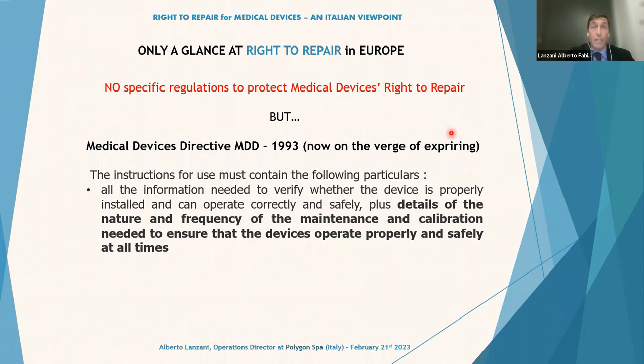If we talk about medical devices, we refer to the Medical Devices Directive, born in 1993, now on the verge of expiring and being amended by a new regulation. The first Medical Device Directive clearly stated that manufacturers need to release and make available details of the nature and frequency of maintenance and calibration needed to ensure the safety and functionality of the devices.